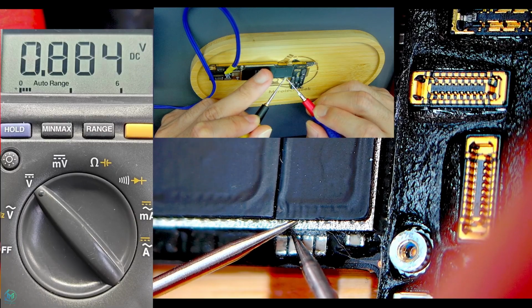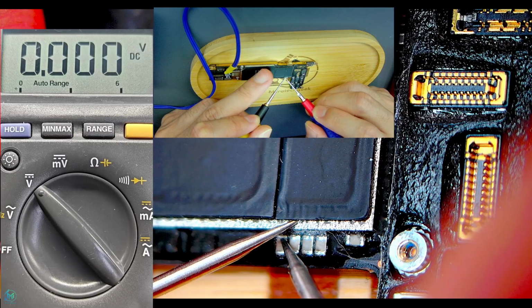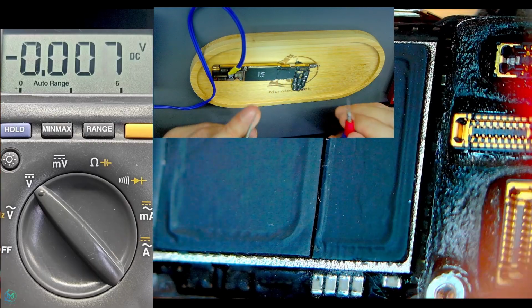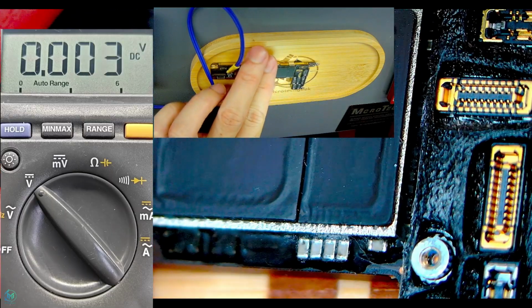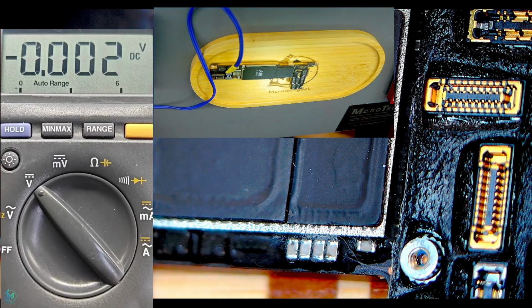So that's the basic principle of using the multimeter in voltage mode. We identify a ground point for the negative probe, touch the positive probe to the spot we want to measure, and compare the reading with the schematic. If the measured voltage matches the expected value, we can confirm that the power supply for that point is functioning normally.